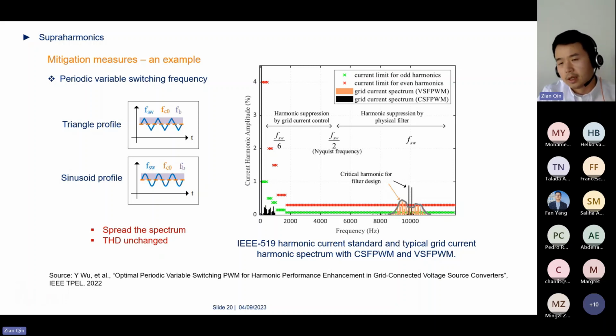We don't have an emission level for supraharmonics yet, but standardization is ongoing. Assume we will have one, similar to the low frequency emission level. They draw a horizontal line for a certain frequency range, and all harmonics should be lower than this line. With variable switching frequency, since the switching frequency noise is more evenly distributed, it's easier to fulfill the limit, if there is going to be one, and I believe there will be in the near future.